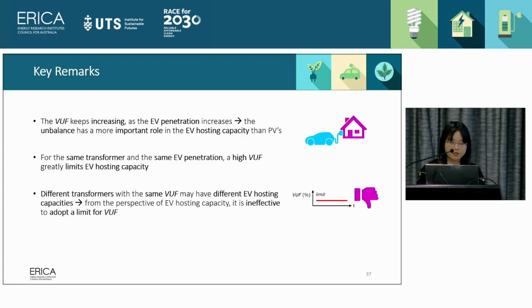So now go to the key remarks. First, the voltage imbalance factor keeps increasing as EV penetration level increases. This means that imbalance has a more important role in the EV hosting capacity than PVs, as PV will be imbalanced only at high PV penetration levels. The other is that for the same transformer and the same EV penetration level, a high voltage imbalance will greatly limit EV hosting capacity. And also the most important one, different transformers with the same voltage imbalance factor may have different EV hosting capacity. From the perspective of EV hosting capacity, it is ineffective to adopt a limit for the voltage imbalance factor. So that's all from my side.